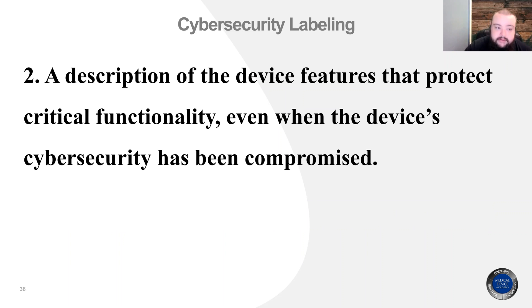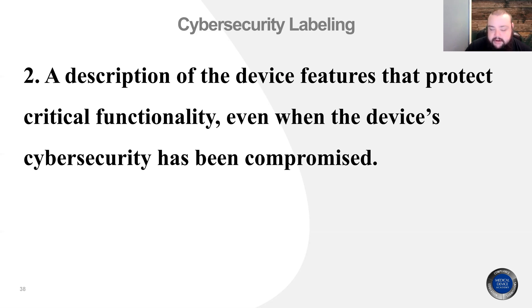For recommendation number two, the FDA suggests including a description of device features that protect critical functionality even when the device's cybersecurity has been compromised. For example, most ambulances have a LIFEPAK — a combination AED-ECG machine. In the event of a cybersecurity compromise, the critical functionality is the manual ECG and defibrillator. You need to make sure those features are protected even in a compromise, so that if login credentials are compromised and users can't send digital information, it still functions as an AED.